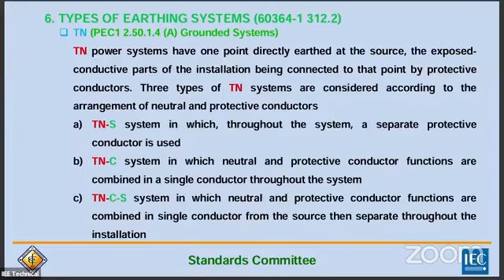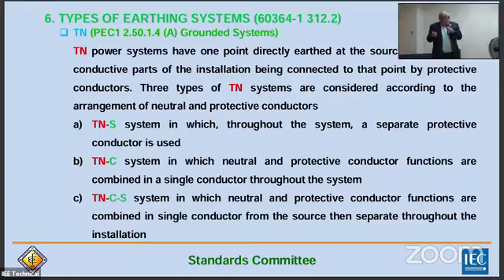Protection ang gamit niya. 3 types of TN systems are considered according to the arrangement of the neutral and the protective conductors. TNS, system in which throughout the system a separate protective conductor, so meron kang separate yung PE throughout the installation, naka-distribute yun. Then yung TNC, system in which neutral and protective conductor functions are combined in a single conductor throughout the system, ito yung PEN. Then the TNCS, system in which neutral and protective conductor functions are combined in a single conductor from the source, then separate, maghihiwalay sila, from TNC, pag the installation mo, kukuha ka ng voltage from line to neutral, so mag-i-split sila.